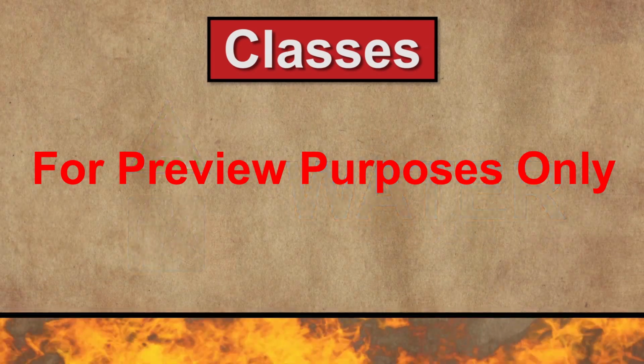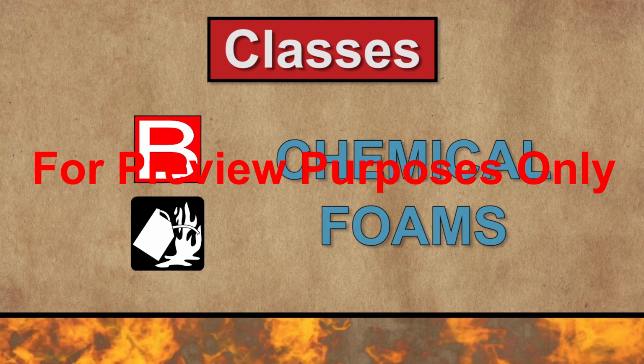Class A fires involve everyday solid combustibles like paper and wood. These can be extinguished with water. Class B fires involve flammable gases, liquids, and some plastics. They are usually extinguished by applying chemical foams. Fires fueled by materials such as isopropyl alcohol, cleaning supplies, disinfectants, and anesthetic gases that are commonly used in healthcare facilities are all Class B fires.